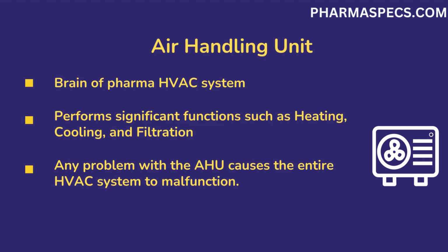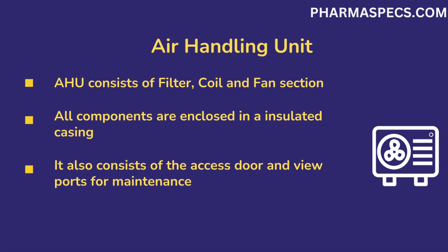Air handling unit. Air handling unit is the brain of HVAC system. It performs major operations such as heating, cooling, and filtration. It is also used to control humidity in an area. If there is a problem with the AHU, the entire HVAC system becomes faulty. So, for optimum performance, AHU must remain in proper working condition. Important components of AHU consist of filters, coils, and fan. These components are installed at their dedicated locations and sections. AHU is also provided with access doors and viewports to view the internal section and for maintenance purpose.